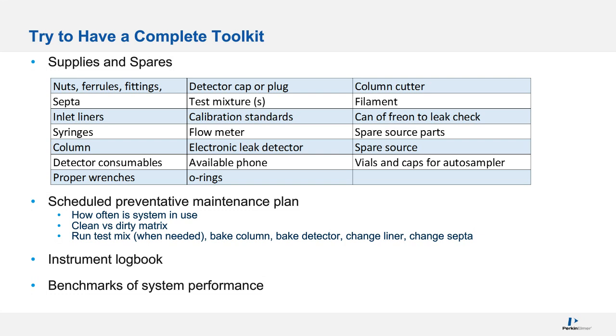The other thing is proper wrenches. We want to use the proper size wrench for the fitting that we need to snug. So if we're snugging the fitting at the mass spec side, which is the 1/16-inch fitting, we don't want to use a channel lock because we would overtighten and perhaps hurt the transfer line, hurt the threads, but we would probably squish the ferrule. Squish is a technical term. I don't like adjustable wrenches because they always move on me, so I always use fixed wrenches when I'm tightening and always have the correct size.